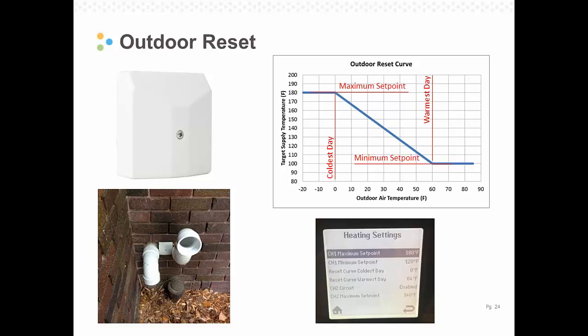Then as the outdoor air temperature warms, fewer BTUs are needed by the home to stay hot, and so that supply water temperature can be reduced. In this case, at the factory default, the warmest day was set to 60 degrees outside with a minimum boiler supply water temperature of 100 degrees. Adjusting these parameters and ensuring that they're reasonable can get you lower and lower supply water temperatures, and therefore lower and lower return water temperatures and increased efficiency.